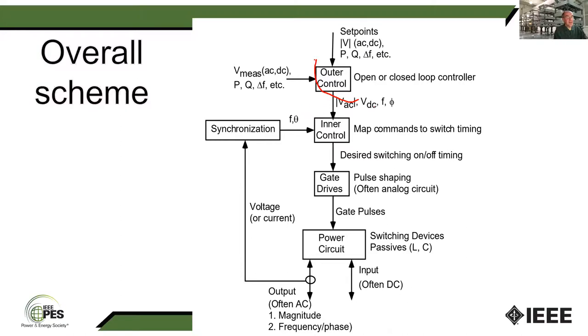And so if the voltage falls, then instead of having this Q reference being set for unity power factor, the converter would supply reactive power to boost the local voltage. And that makes it easier to keep the resource online, supplying power to the power system when the voltage is lower, if you're boosting reactive power to raise the voltage. And so the low voltage ride through really comes in as changing this set point.